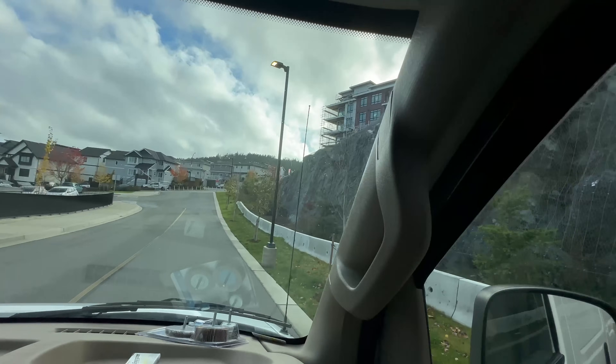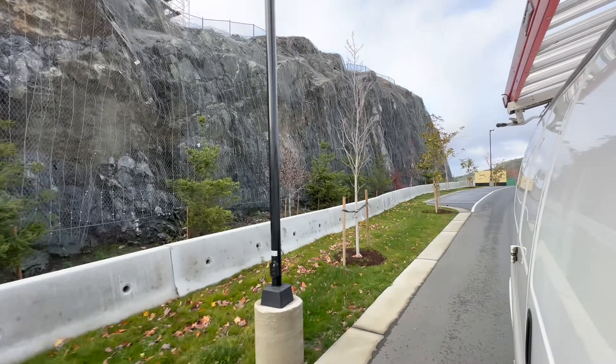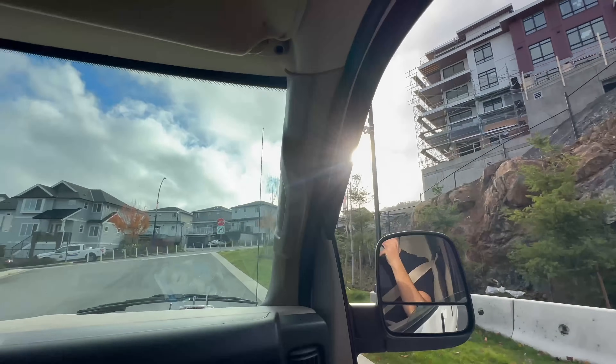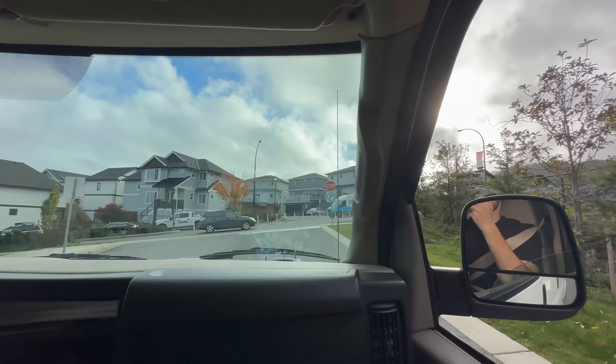Power just came back on — the parking lot lights are back on. Once that goes through its utility check and cool-down time, it will first transfer back over and then enter a cool-down period. With the interesting part of the video over, I want to do some explaining and answer questions. Power was probably only out for an hour at most, and everything worked as it should have.